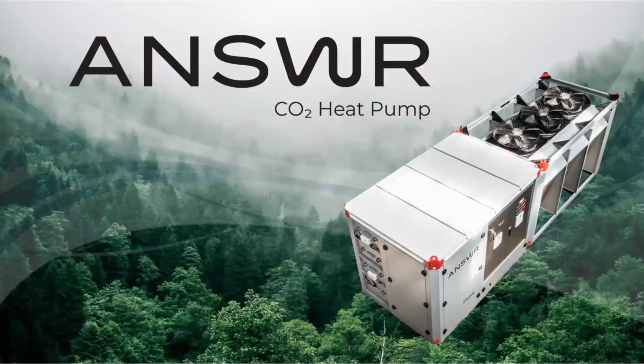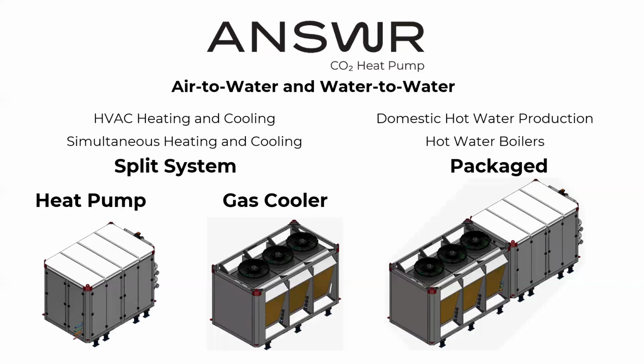And that's where we built our ANSWR CO2 heat pump. This is an air to water and a water to water system inherently. You can do refrigeration as well because we're using the exact same components that the supermarket and industrial industry has been using for 30 years. We've specifically designed it for HVAC duty first, then extended that operational range so it can encompass a lot of these complicated refrigeration projects that play on the edge of refrigeration, HVAC, and heating systems. We can do domestic hot water without a problem. Simultaneous heating and cooling is really new, novel, and unique because we built a non-reversing system, and we can do hot water boiler applications with it. You can set up a split with long distances between units, or do it as a package system.